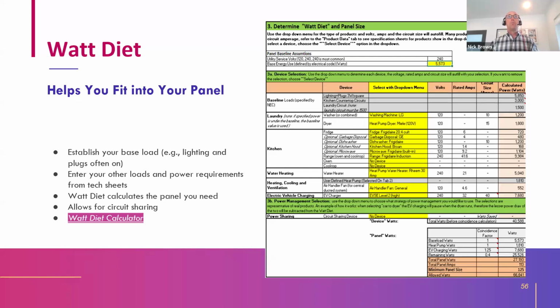So it's a way of double checking your electrician, because some electricians, believe it or not, don't do the full calcs. They take a look at the size of your house and say 200 amps, when in many cases we find 100, 125, or 150 amps are adequate, even for all-electric designs with EV charging as shown here, even for heat pumps and heat pump water heaters.